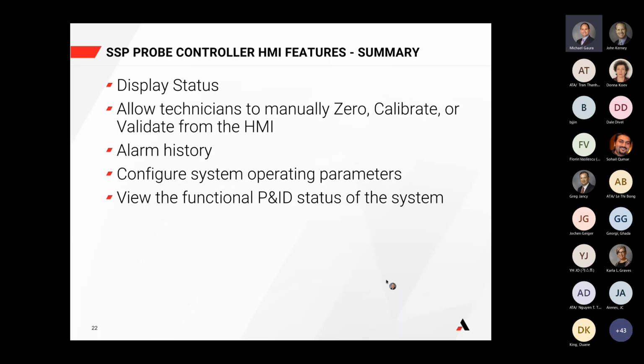So my final walkthrough on the probe controller here is just, again, what are the features, and what do we have going on there? It's not stated here, but hopefully it's obvious that the controller is basically the brains and the heart of the system. It's doing a lot of the thinking and a lot of the processing, and ultimately it's the backbone for providing a status message on a touchscreen interface that's sitting there. It allows the technicians to do various functions and set up different automated features and various settings, including setting alarm points, and even drive the various mechanisms like a zero or a calibration or validation directly from it, and not have to get into the analyzer itself.